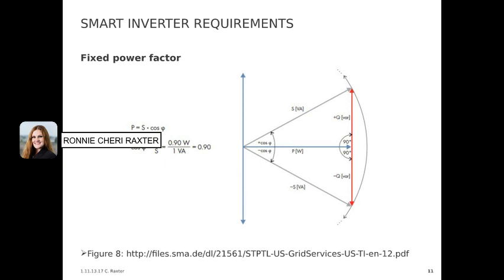The next setting is fixed power factor. Unlike the ones that we have discussed thus far, this setting is deactivated. This functionality would require the DER inverter to continuously supply reactive power at a fixed power factor cosine phi. This would be beneficial in locations where the utility knew there were heavy loads that consumed VARs, but if it was not such a location, then it could be reducing the output of the smart inverter and essentially injecting VARs where it wasn't necessary. This is ultimately deactivated because it's treating the cause, not the symptom, and it's either volt-VAR or a fixed power factor. And the volt-VAR function, which is only implemented when the voltage dictates so, is more valuable in regard to maintaining grid stability.